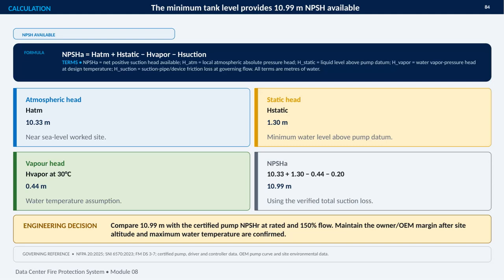This slide calculates the net positive suction head available, or NPSH, for the fire pump under the governing minimum level condition. The formula is atmospheric head plus static head, minus vapor pressure head and suction side losses. Each term is expressed in meters of water. For this worked site, the atmospheric head is 10.33 meters, based on near sea level conditions. The minimum water level contributes 1.30 meters of static head. At the assumed water temperature of 30 degrees Celsius, the vapor head is 0.44 meters. Finally, the verified total suction loss is 0.20 meters.